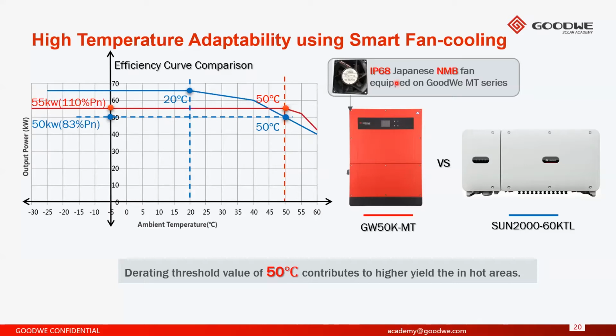These fans are variable speed fans. So the inverter is smart enough to control the fan speed by virtue of the temperature that is measured in the ambient and the internal temperature as well. So at the highest temperatures, the fans will be running at their highest speed, and they will reduce speed at lower temperatures. So this also reduces the wear and tear on the fans and reduces the risk of the fans failing over their lifetime.